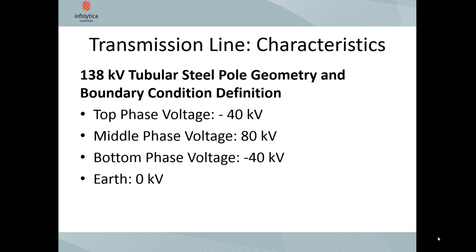Finally, we also need to define the sources. The report requires that the mid-phase be at 80 kilovolts and that the top and bottom phases be at minus 40 kilovolts. This corresponds to an instant in time, and so we will be using static analysis to examine this situation.